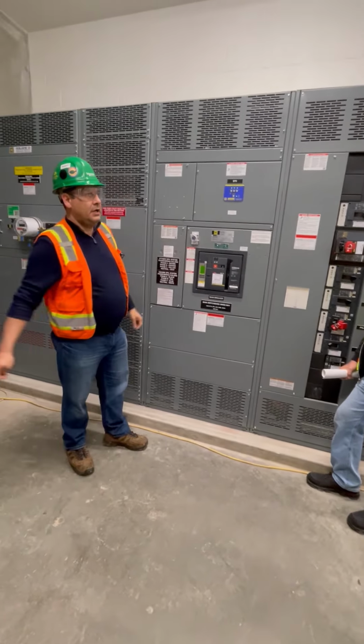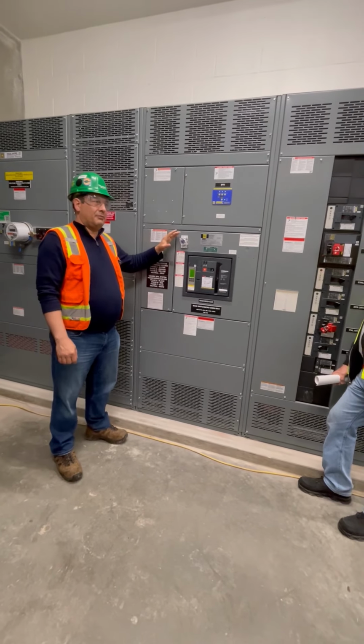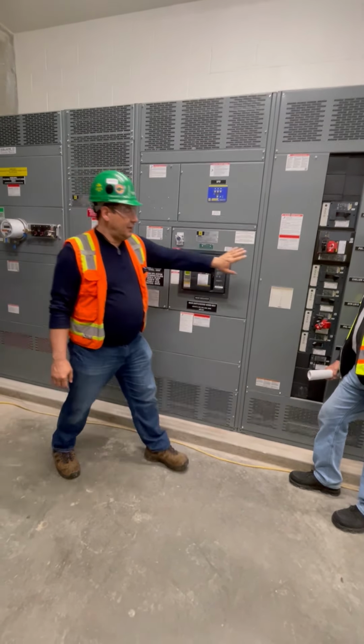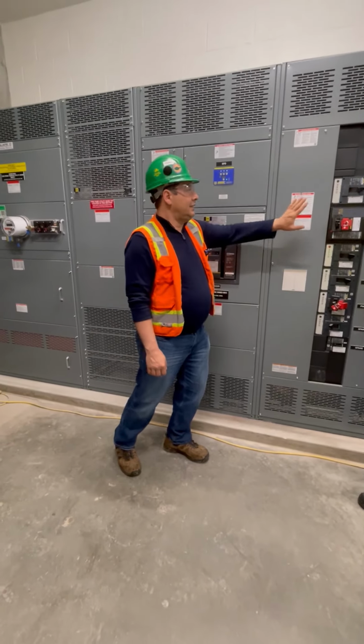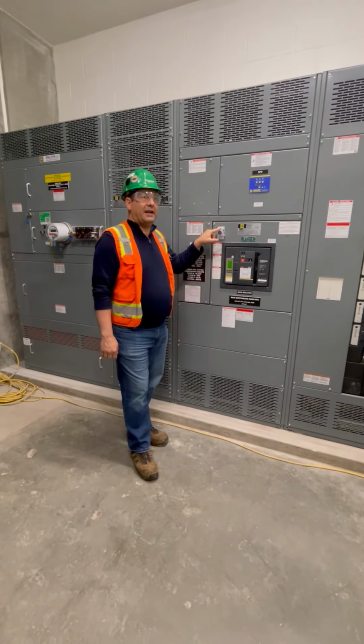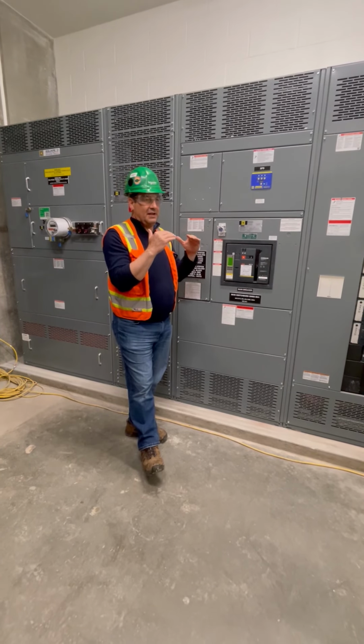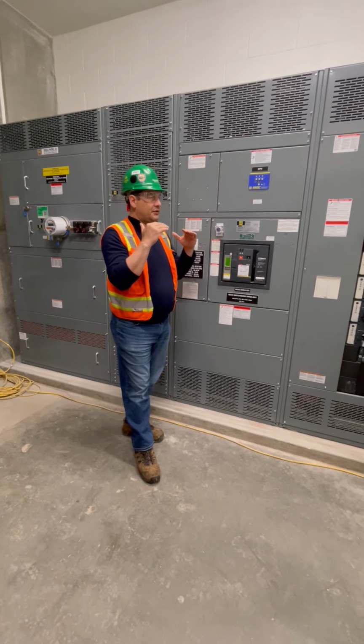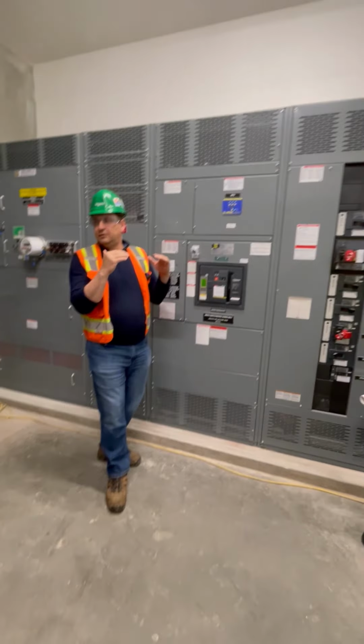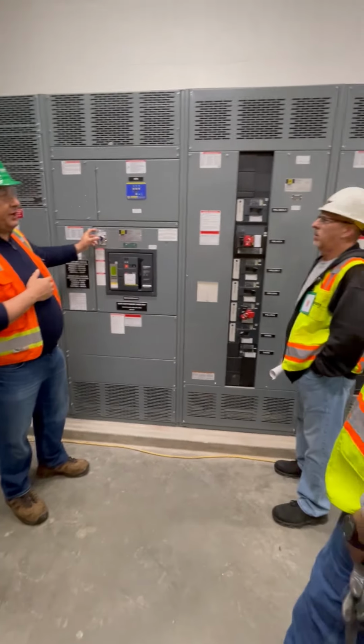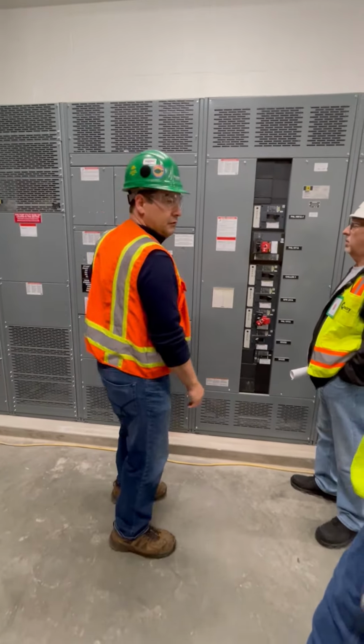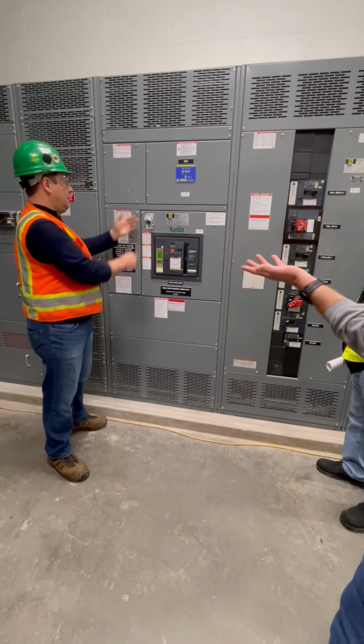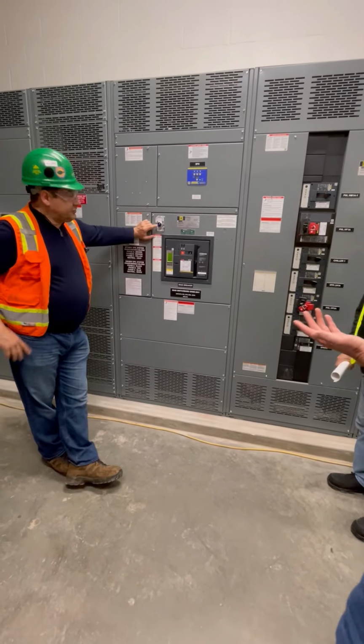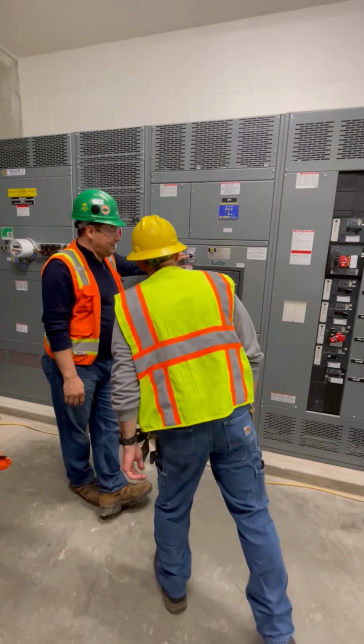Everything downstream from here. Now, like I said, by code, any 1200 amp breaker requires it. So if this is a 3000 and you had a 1200 amp feeder over here, then that feeder would also be required to have one of these by code, because any breaker that's 1200 amps and above requires arc flash reduction, some kind of mitigation. And like I said, you may want to check with Perry to turn the breaker on. How do you know that's not active right now? Don't we see the switch? How do you know it's not active? The light's not on. This comes on blue. There's an LED in here. Oh, it turns blue.